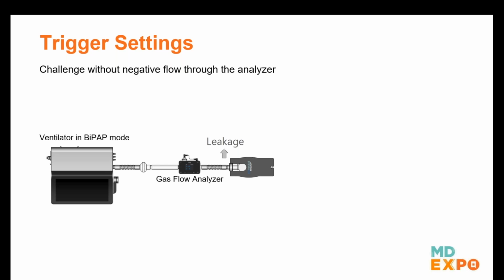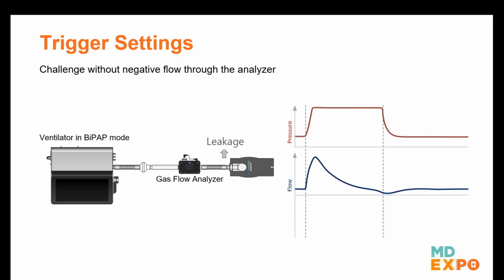In this application, when the ventilator applies the higher pressure level, there's going to be flow through our gas flow analyzer, volume filling up our test lung, and then when it releases the pressure, the volume is actually leaving through this leakage and not flowing back through our analyzer. So remember, the default trigger settings we talked about earlier are no longer going to work, because we never have negative flow through our gas flow analyzer. In this situation, our pressure and flow curve look, for example, like this. As you can see, our flow waveform is not sufficient for triggering due to the lack of a steep rising or falling edge at the end of the inspiration phase.